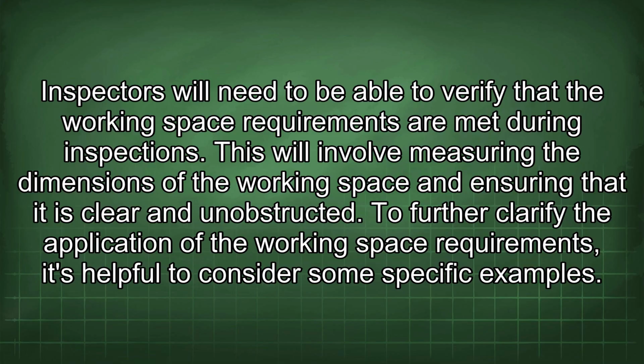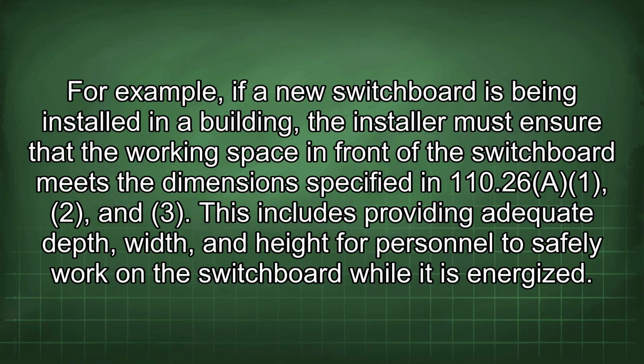To further clarify the application of the working space requirements, it's helpful to consider some specific examples. For example, if a new switchboard is being installed in a building, the installer must ensure that the working space in front of the switchboard meets the dimensions specified in 110.26(A)(1), (2), and (3). This includes providing adequate depth, width, and height for personnel to safely work on the switchboard while it is energized.